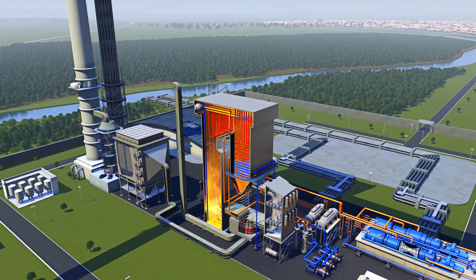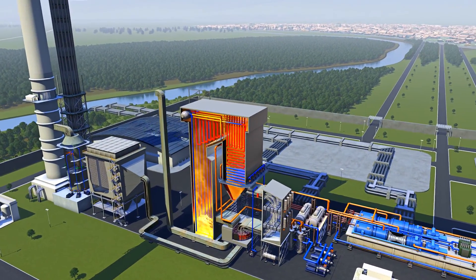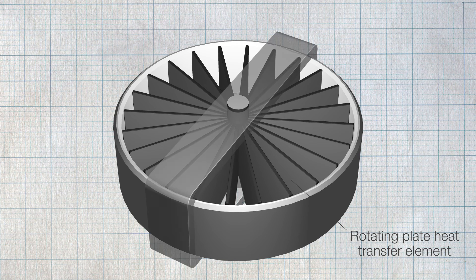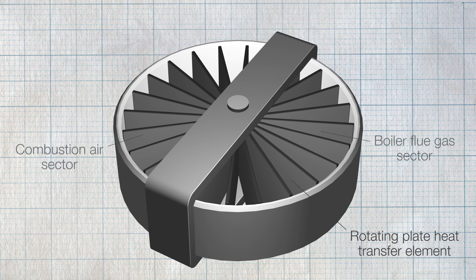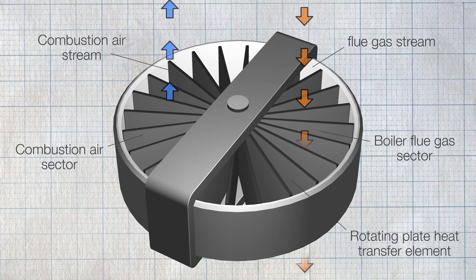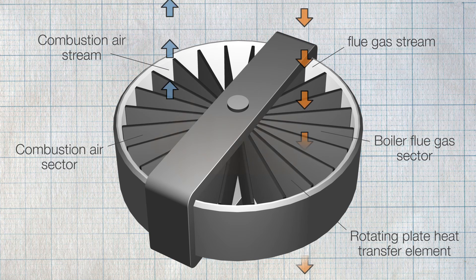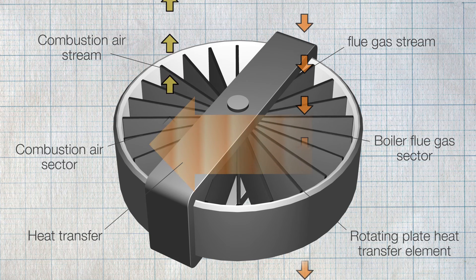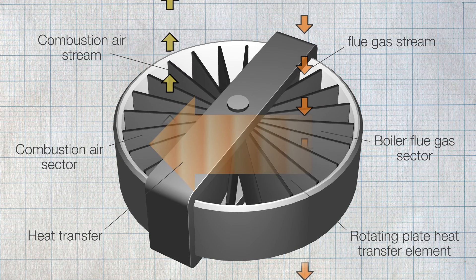Rotating plate air preheaters are commonly installed in many power stations. They comprise of a rotating plate, heat transfer element and between 2 to 4 sectors, which are used to recover heat from the boiler flue gas. The heat transfer section of the preheater rotates at up to 3 RPM, collecting heat from the flue gas stream and releasing it to the boiler air stream.